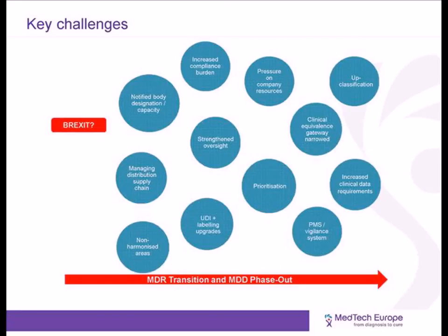Post-market surveillance and vigilance activities will be directly subject to notified body assessment, and those notified body assessments will themselves be subject to scrutiny by supervising authorities at national level. Under the MDR, manufacturers will have to operate systems for preventive risk management and a post-market surveillance system which is proportionate to the risk class of the product, appropriate to the type of device, and based on a documented post-market surveillance plan. The post-market surveillance system will have to be suitable to cover the whole product lifetime and will form part of its ongoing clinical evaluation, along with post-market clinical follow-up data, which manufacturers must also gather and evaluate.